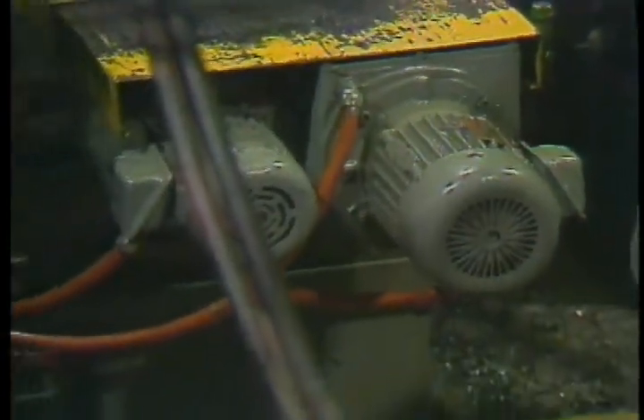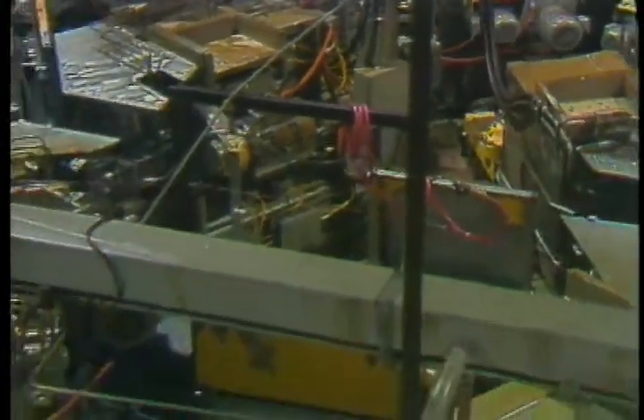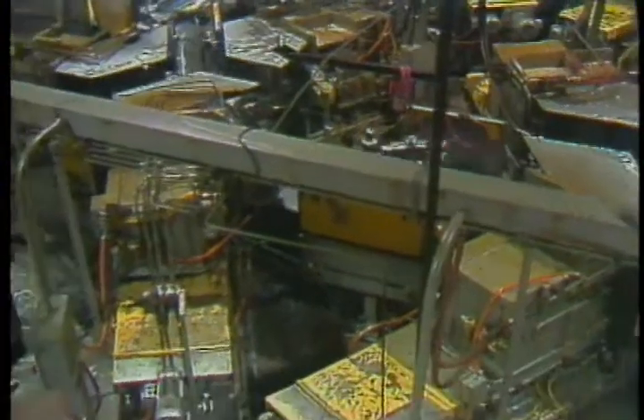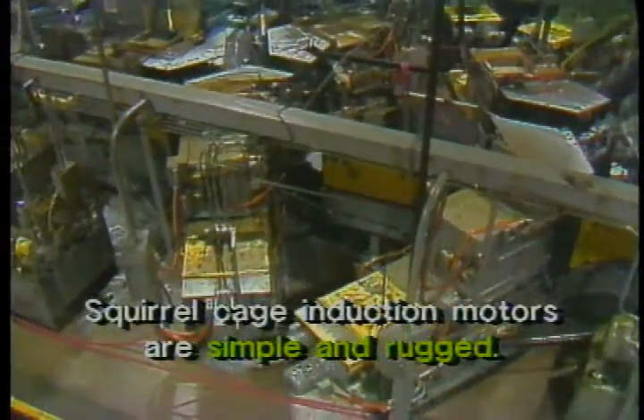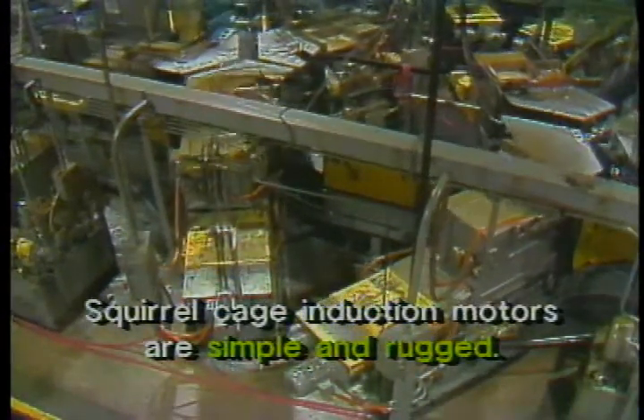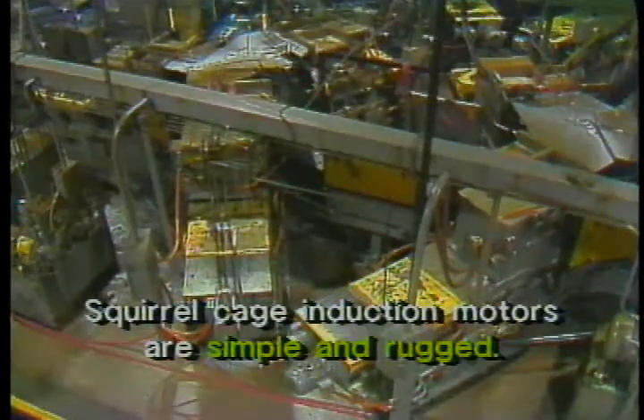Three-phase squirrel cage induction motors are more common than any other motor type in most industries because they are simple and rugged. There are no commutators, brushes, capacitors, or other components to go bad or need maintenance, and no rotor windings to short out or open.